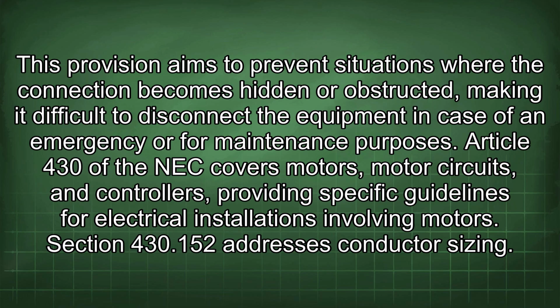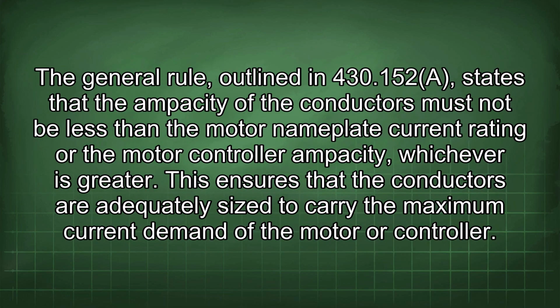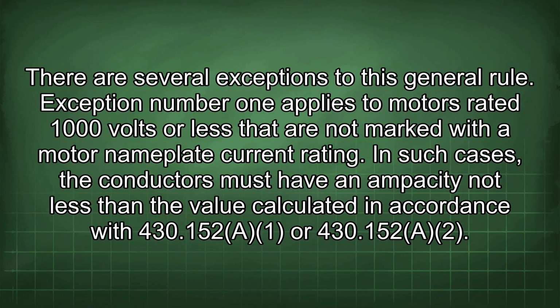Section 430.152 addresses conductor sizing. The general rule, outlined in 430.152(A), states that the ampacity of the conductors must not be less than the motor nameplate current rating or the motor controller ampacity, whichever is greater. This ensures that the conductors are adequately sized to carry the maximum current demand of the motor or controller. There are several exceptions to this general rule.